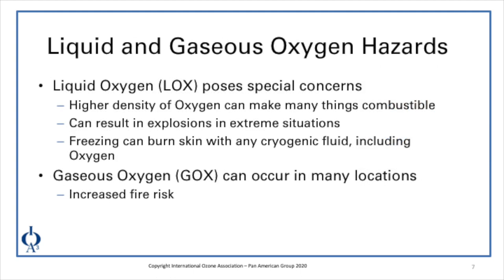Taking a look at specific liquid and gaseous oxygen hazards, liquid oxygen poses special concerns. The higher density of oxygen can make many things combustible that would otherwise not be combustible in air. It can result in explosions in extreme situations, and freezing can burn the skin from the cryogenic fluid. If you get exposed to liquid oxygen itself, it could burn your skin through freezing. There is another freezing concern with cryogenic liquid oxygen — you often see freezing on the exterior of the pipe, and extended contact with that frozen pipe could also lead to skin burns.